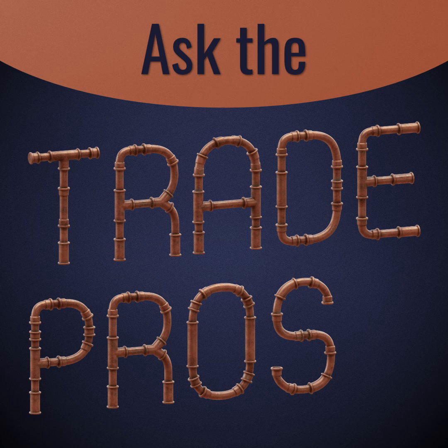I tend to look, I see rust on the panel, if you've got wear on the panel. One of the problems we have out here is a lot of panels that are discontinued or no longer available. They're either models like Federal Pacific that have lost their UL rating and should be replaced because they're considered fire hazards, or they're just brands that are out of date and you can't get the breaker anymore. They have weird sizes, weird locks. As Todd was talking about a little earlier, they connect into that bus bar, and you can't just put any breaker in any box. It has to be the right breaker for that box or it won't connect to that bar correctly, and then you'll have a fire hazard.